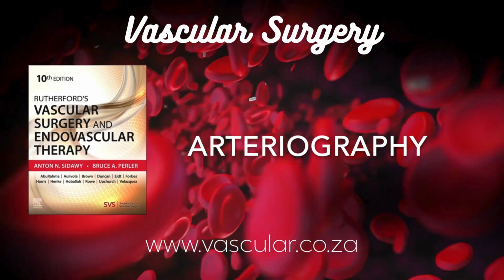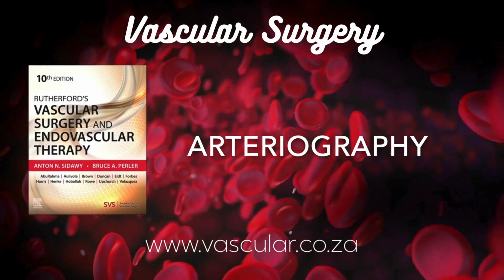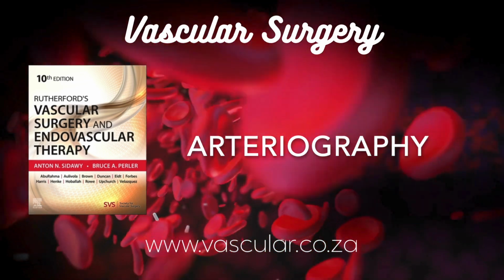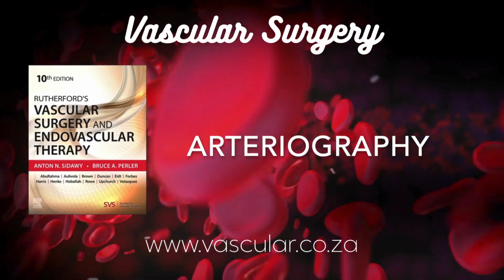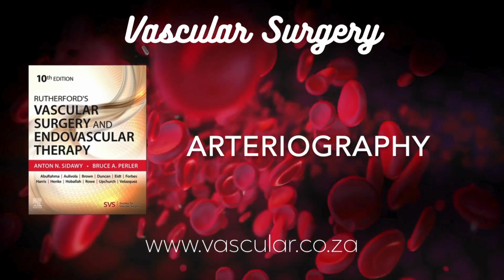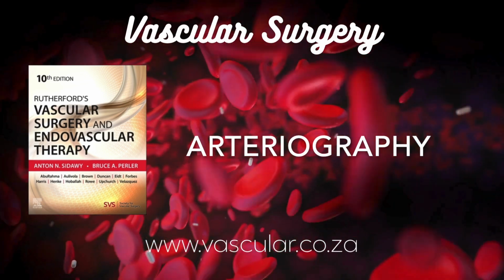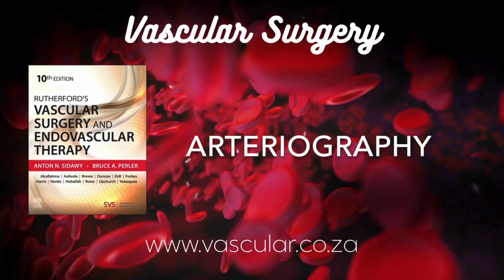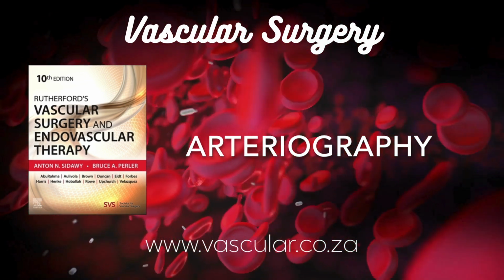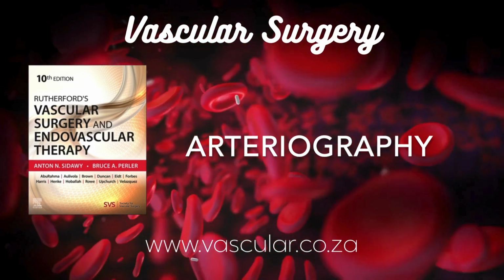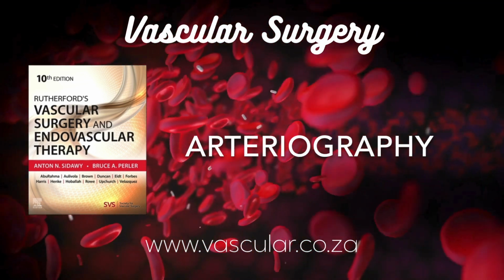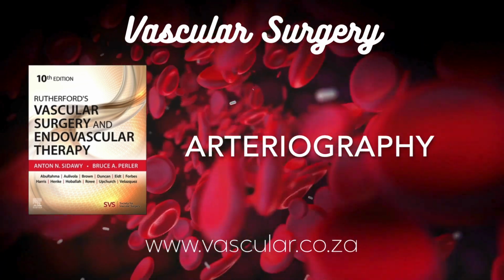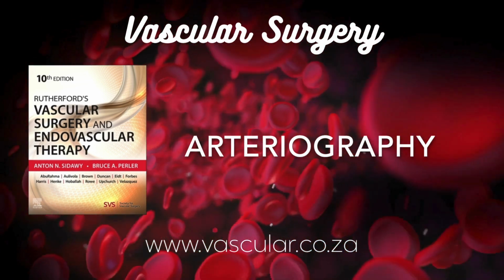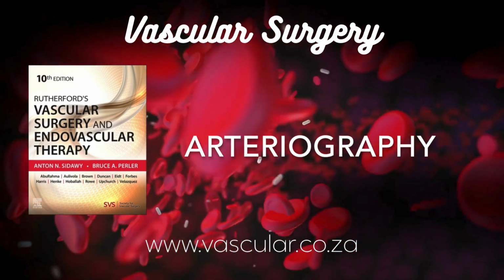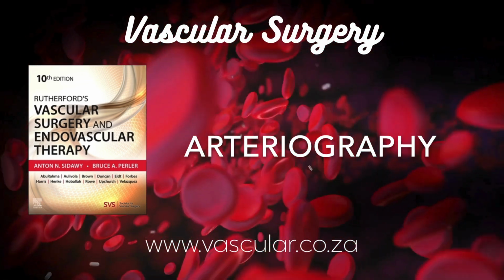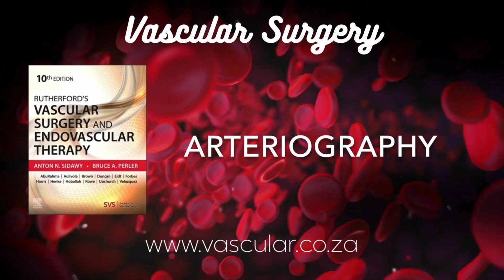Okay, let's move to the imaging hardware itself. Fixed mount versus portable. Beyond mobility, what are the main differences? Well, both types share the basic parts, right? A generator for the X-rays, the C-arm holding the image intensifier or detector, screens to see the images, and the software. Got it. But the fixed mount units generally have more powerful generators. More power means. It means the X-rays can penetrate denser tissues better, so you get more detailed images, which is a big plus in, say, larger patients.